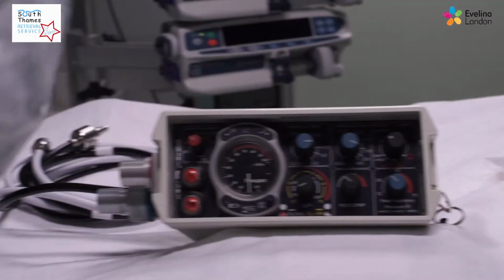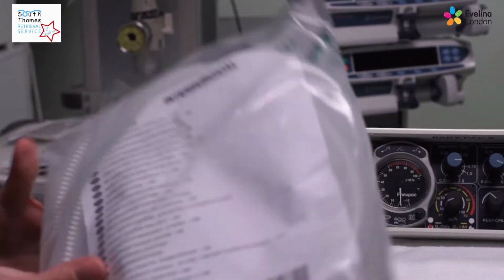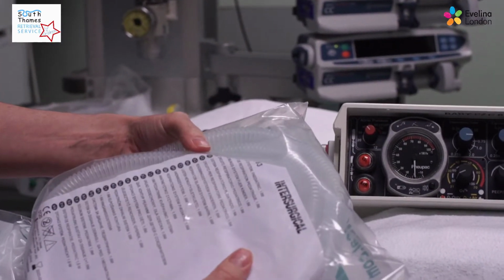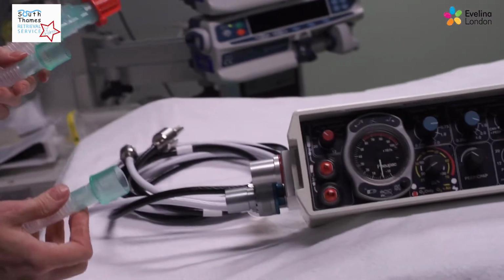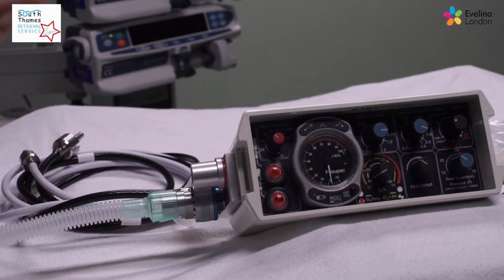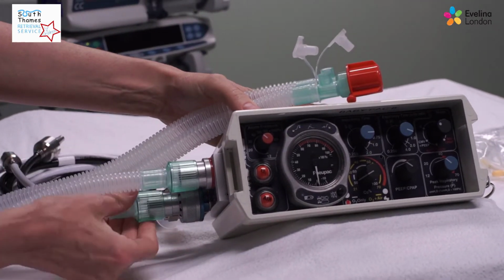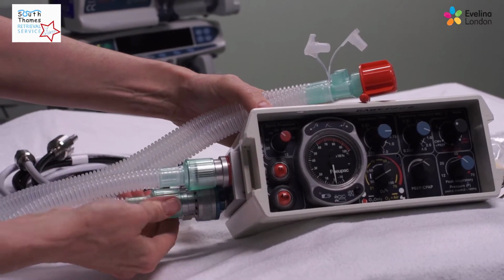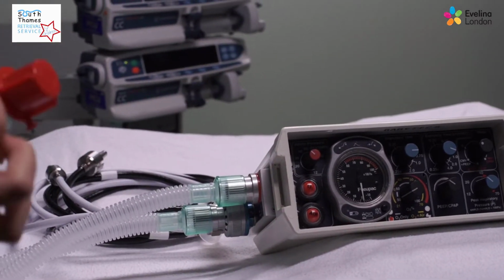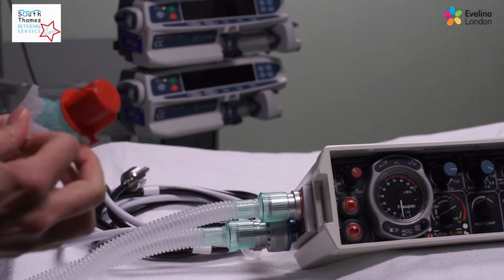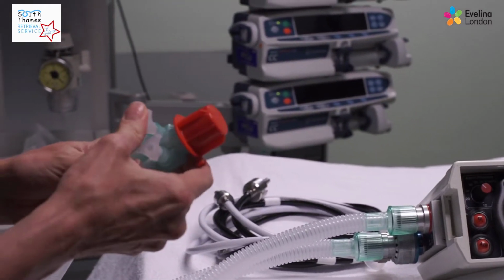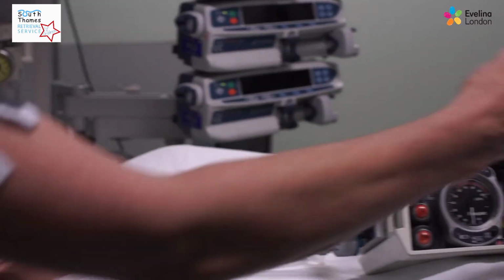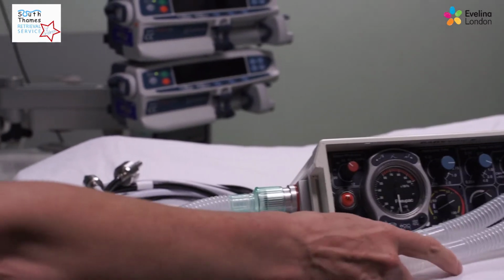Next, we're going to attach the ventilator tubing. We check we've got the correct tubing for this ventilator. For setting up the basic Babypac, it doesn't matter which section is applied to the inspiration or the expiration port. We check that the holes at the end are closed and have a rough look at the tubing to check there's no obvious hole or damage.